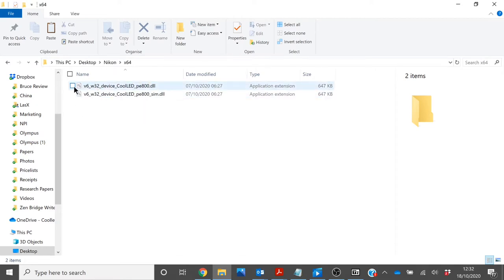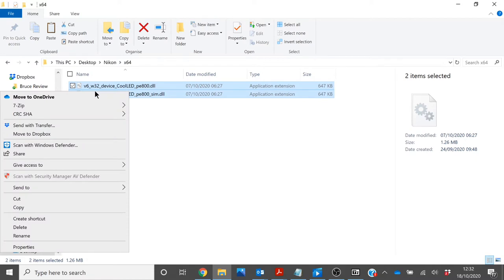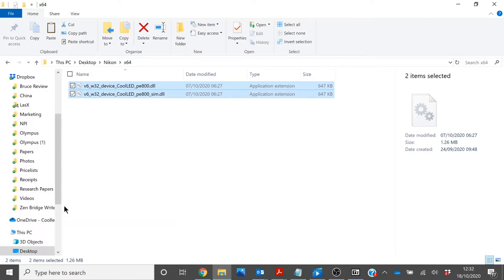You will then need to copy the DLL files. These then need to be saved in the NIS Elements installation folder. The location of this folder is based on how the software was installed, but it is most likely to be found under the C drive in Program Files.